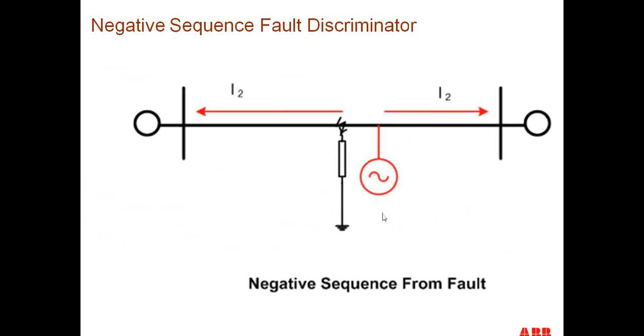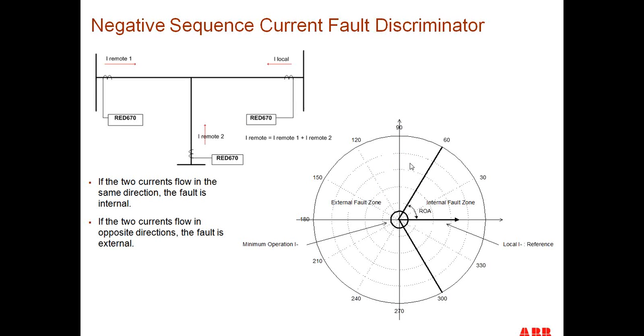Because if it was an external fault, a fault located even on the terminals, then our negative sequence current would be a through current. By our CTs, they would be 180 degrees apart from each other by the way we connect the CTs. But if the fault current was internal, then the currents would be going away from each other, but by our CT manipulation, they're added together. So we get an operating curve where anything to the right of this horizontal line would be an internal fault, and anything to the left would be an external fault.